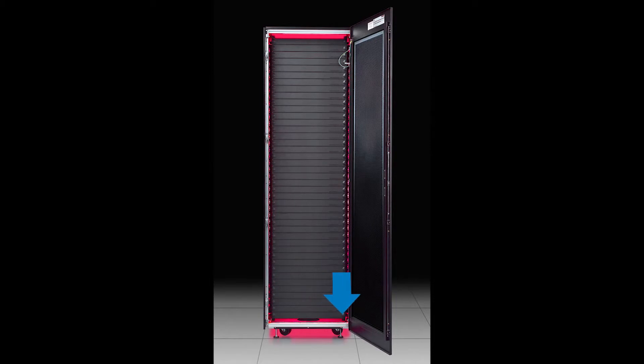Optimizing your data center for airflow management starts with the rack. There are five critical areas where racks tend to leak: beneath the frame, to the right and to the left of the internal rails, below those rails, and also above them.